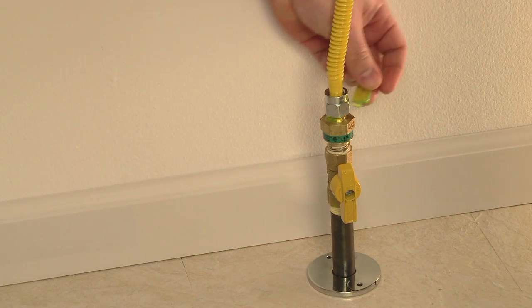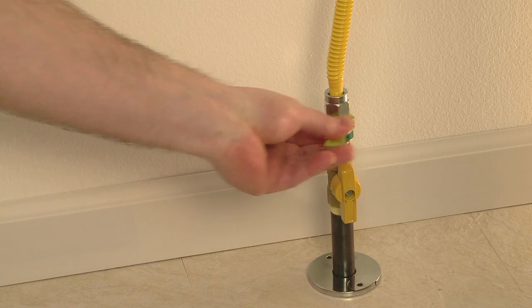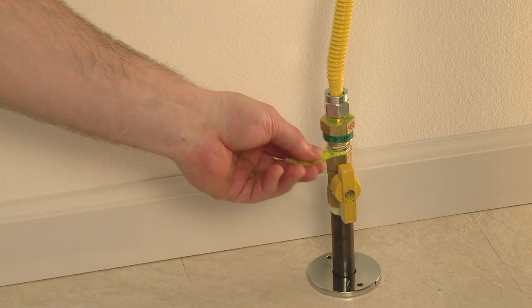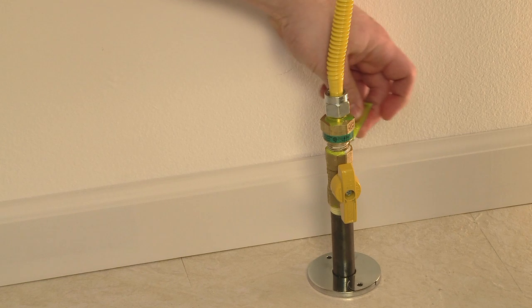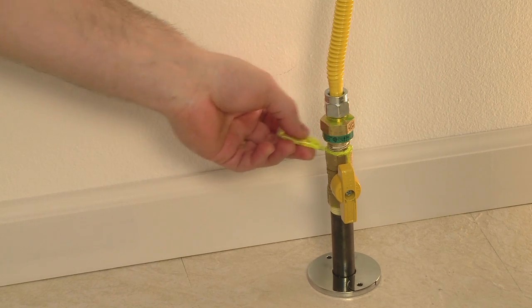With the leak detection solution in place, check all connections for bubbles. If bubbles are present, immediately close the gas shutoff valve and tighten the appropriate connection. Reopen the shutoff valve and if necessary reapply leak detection solution and examine for bubbles once again.